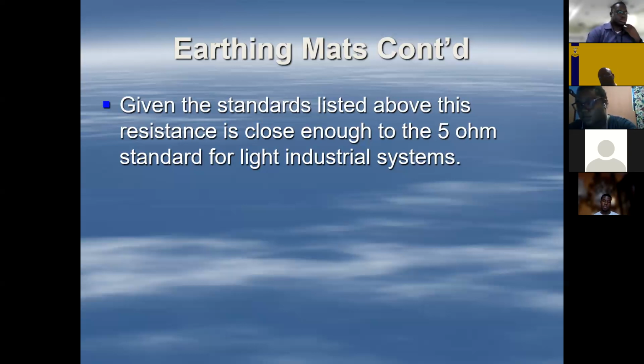So the other option is, you've gotten down to 7 ohms, and you can then tie that mesh to two rods. So you put two rods in and measure your earth resistance. If you were using, for example, copper wire to do this, you would just use the radius of the copper wire.